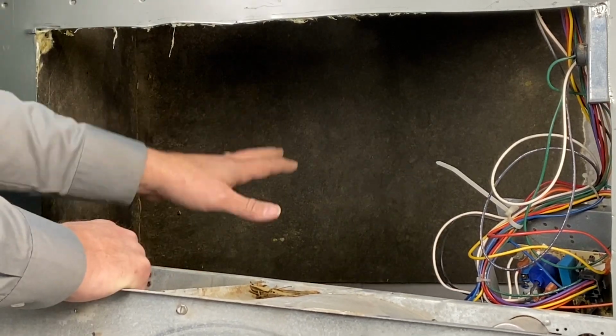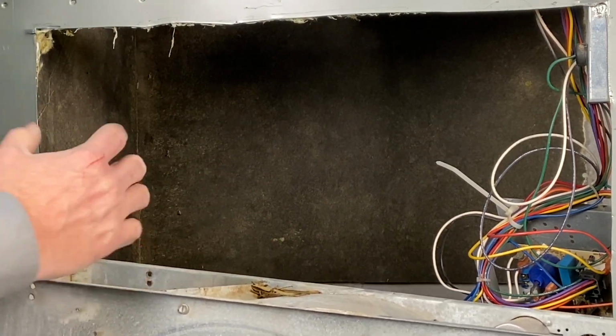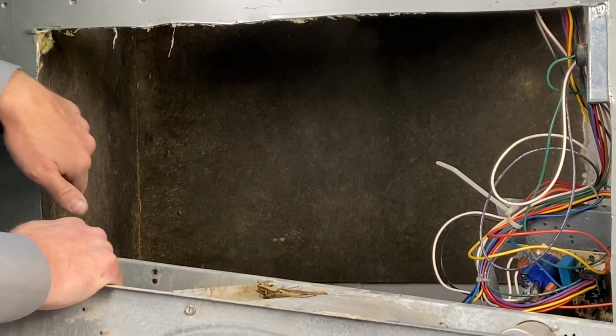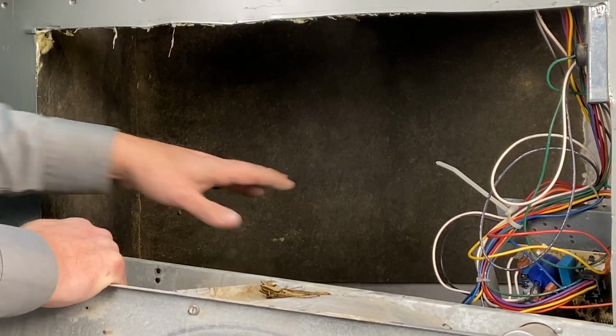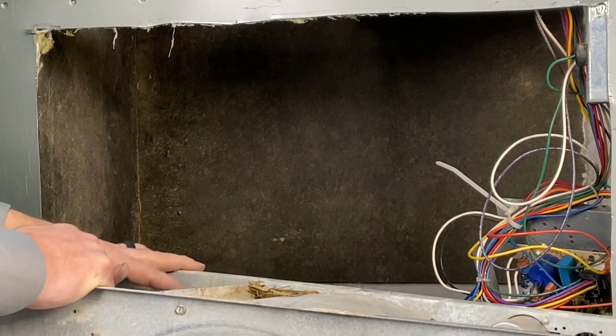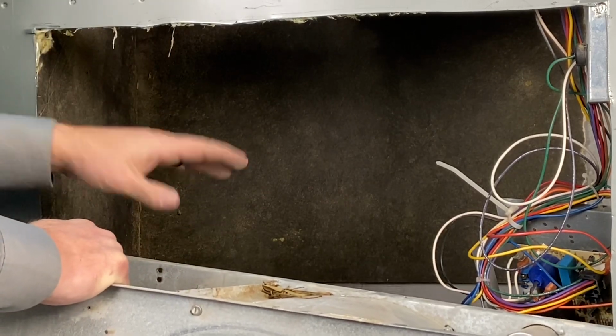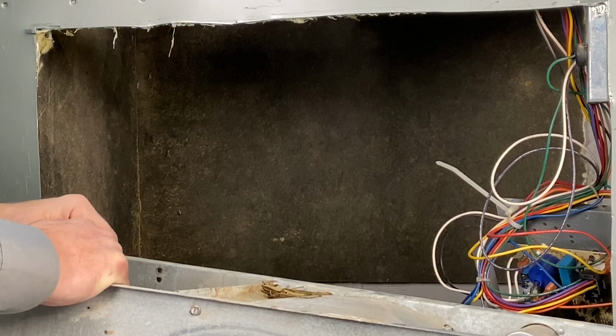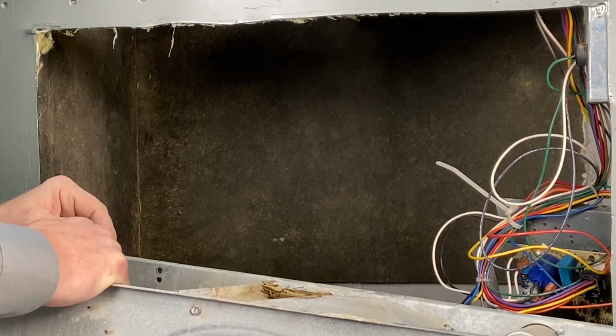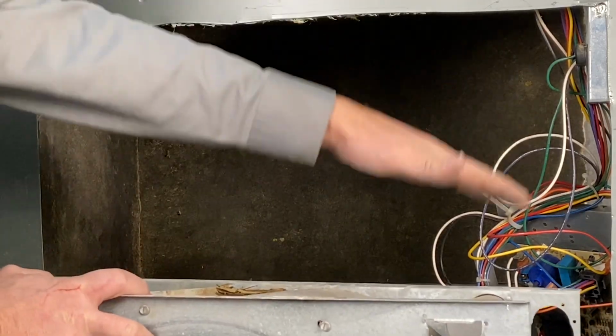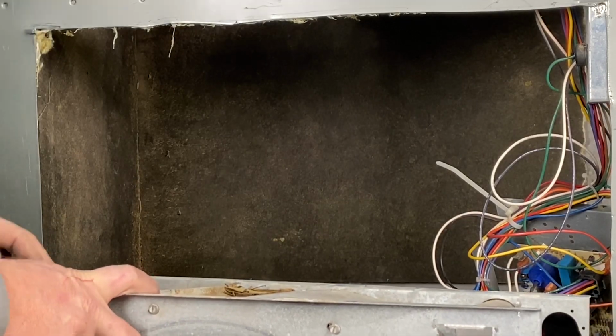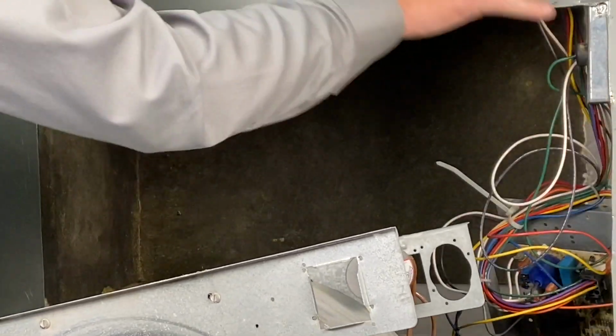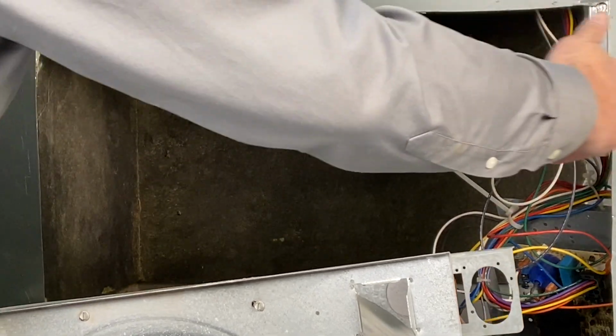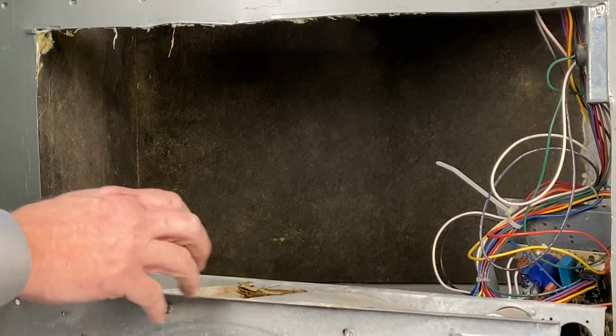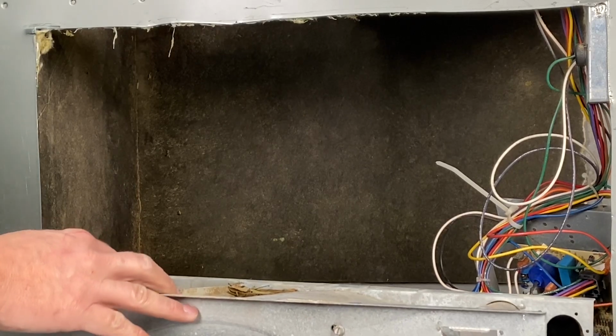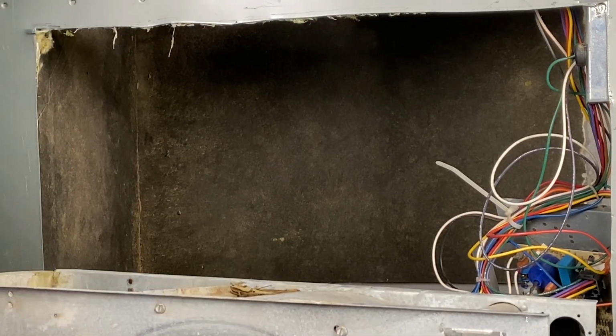So a lot of times they're installing these systems in the attic, and you get all the heat from the attic that's going right through this metal, right to that little bit of insulation inside this housing. So it's definitely an energy issue when you install these units in an attic. So a basement or in a closet is an ideal situation for them. Also, this one has the side cutout. If this was installed in a basement, this very same filter rack would be installed on the side here, so your filter would be on the side. That's also acceptable. But what we're going to do next, we're going to talk about all the components of this blower motor and how we would take it apart and clean it.